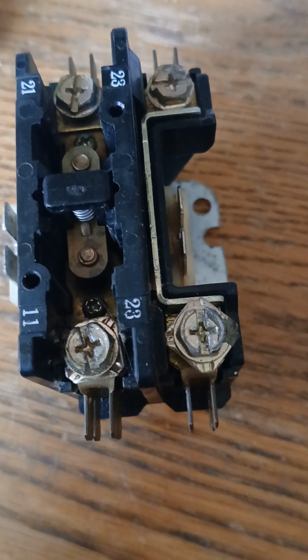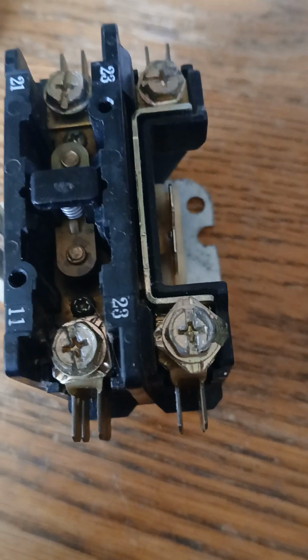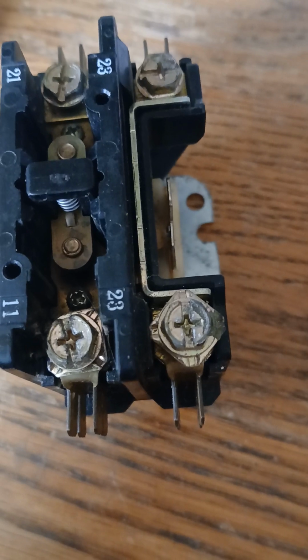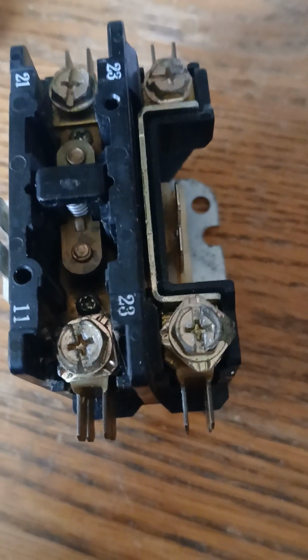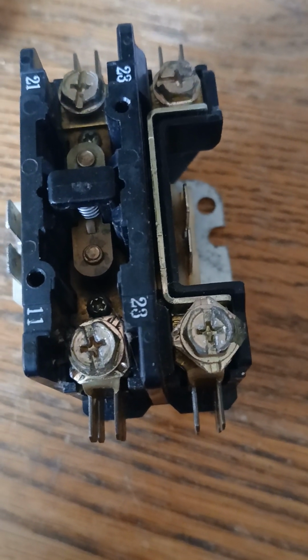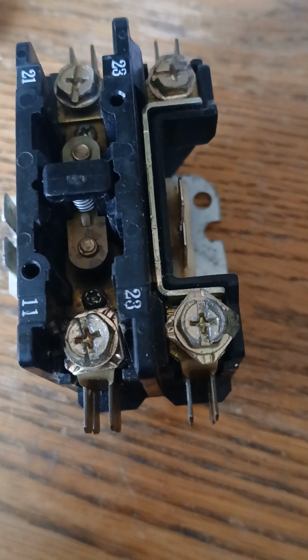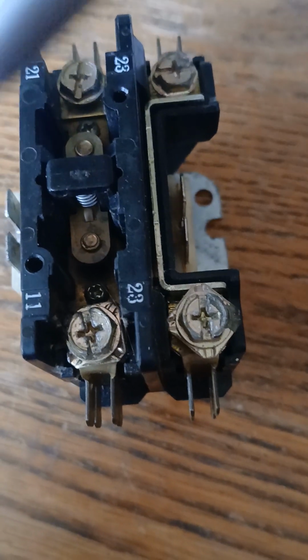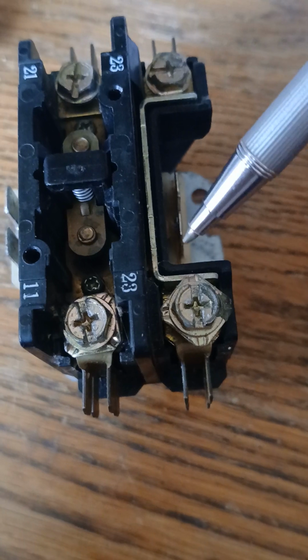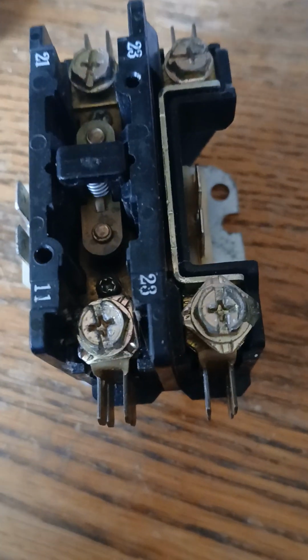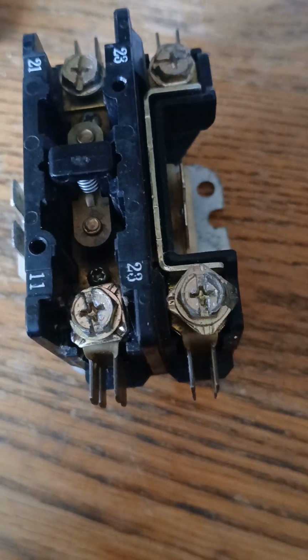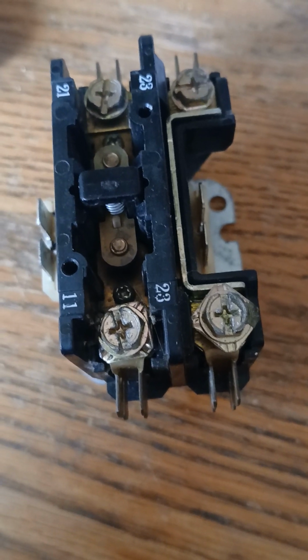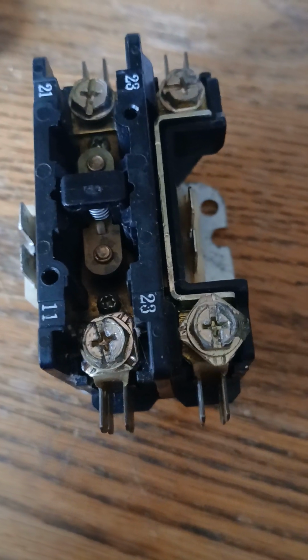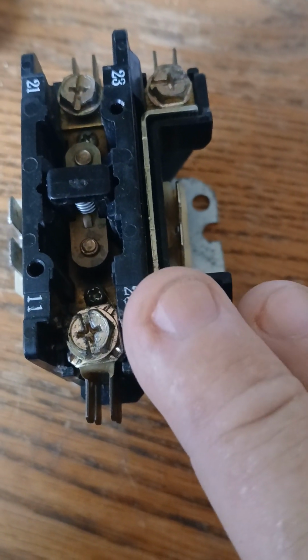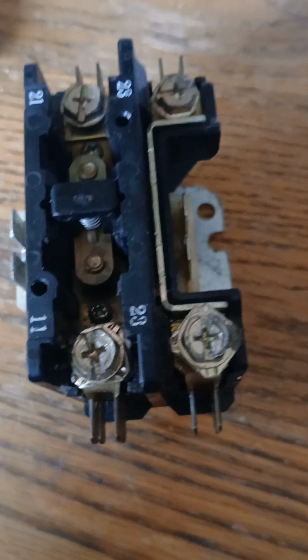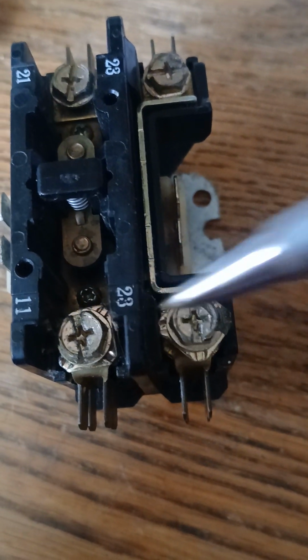So if we're going to operate this, when we bring high voltage in, one way to cut the electricity on and off is this gadget here called a contactor. Essentially, a contactor gets energized by low voltage on the side. This may be yellow, this may be blue, or some people could use red, with blue being the common. The other one would be the hot wire fed off as the thermostat engages and supplies voltage, or from the air handler inside, wherever it comes off the transformer. Notwithstanding, this should be 24 volts. We would have 120 here, 120 here.